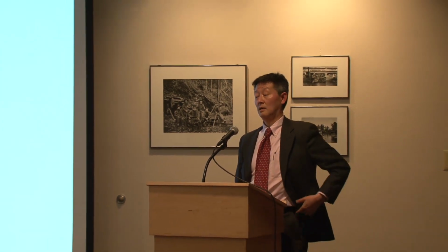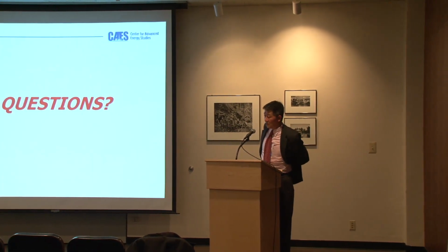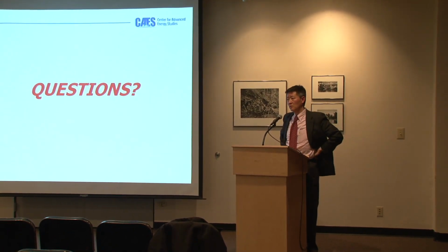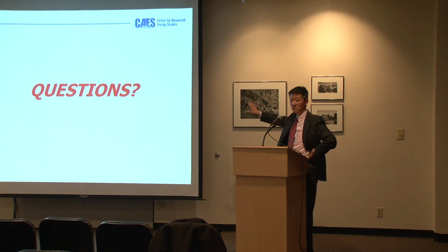Yes? Actually, I had a question. You were talking about getting away from the zirconium-based cladding. What else would you use, or is there something else in use already that they could? No, there's not. There's some history of aluminum-based cladding. There's a grade aluminum 6061 that some research reactors at universities, smaller reactors, use, that's been underwater for 30 years with no corrosion or pitting or anything. It's really remarkably well adapted. But aluminum has a low melting temperature, so you cannot use aluminum as a cladding for high power reactors like the ones we have.